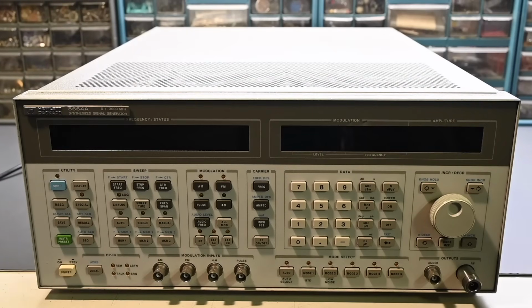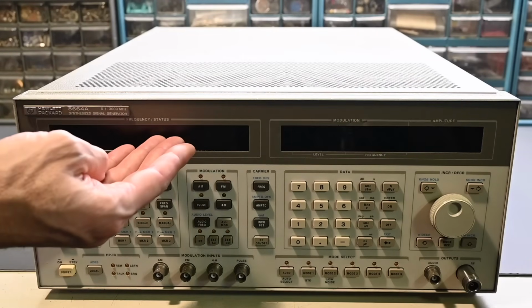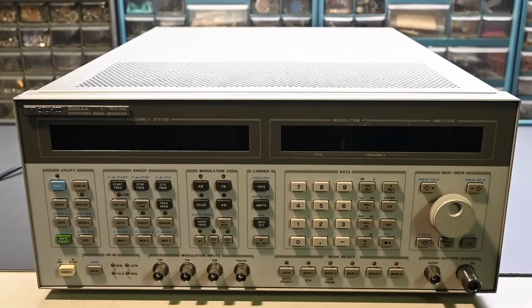Alternately, you could feed in a 10 megahertz signal from an external time base or reference oscillator that's very stable and accurate. But no matter what the source, whether it's internal or external, you don't want the 10 megahertz reference to be drifting whatsoever, because if it drifts even slightly, then even though the display will be showing a resolution down to 10 millihertz, the actual RF output would be slightly off from that value.